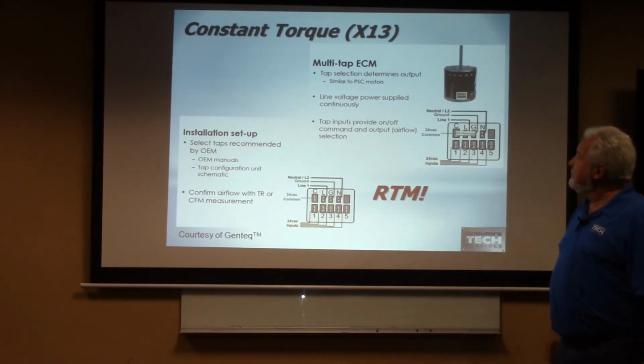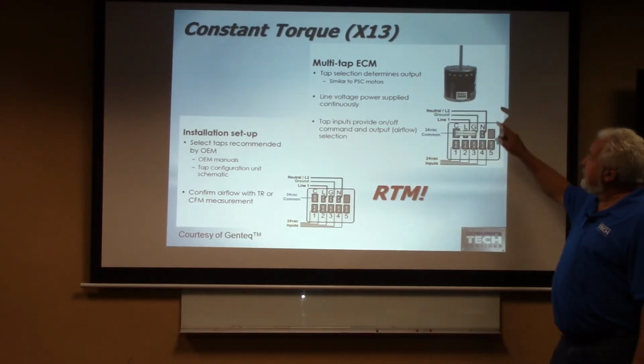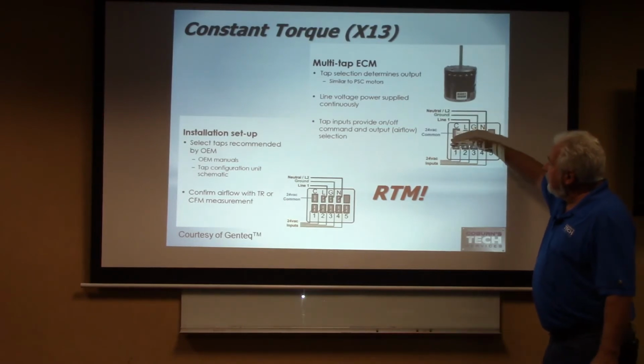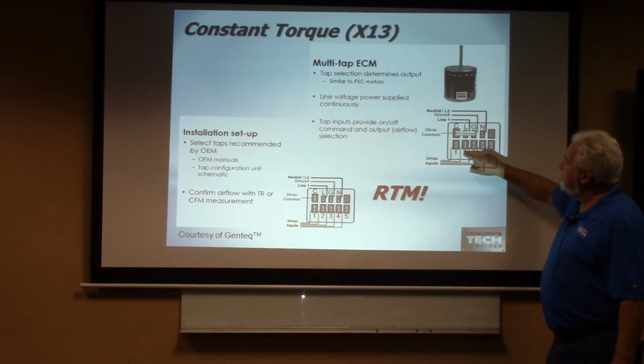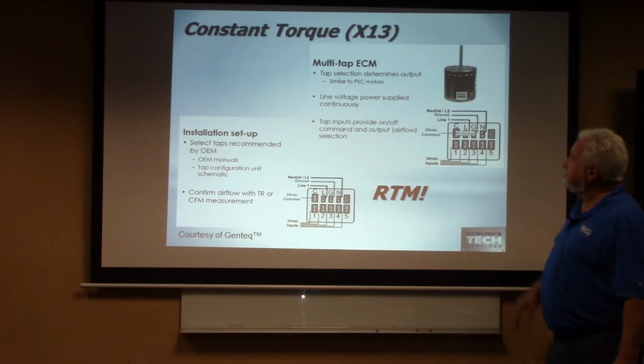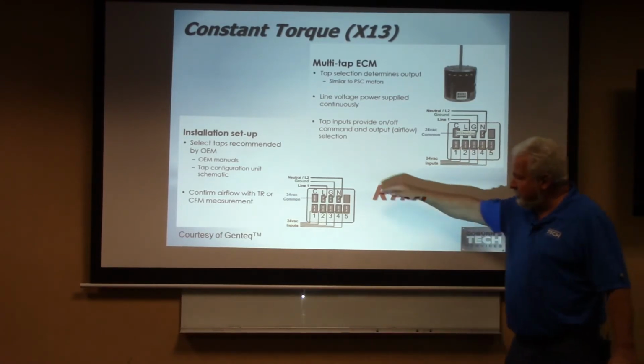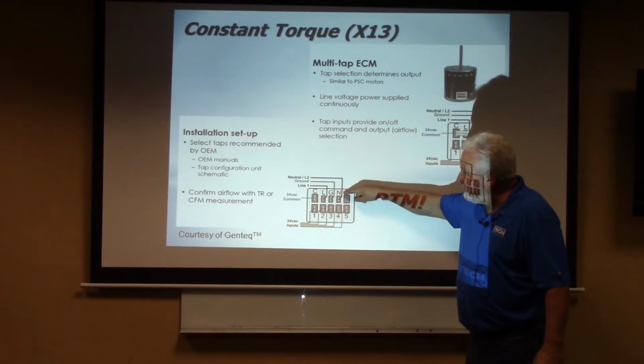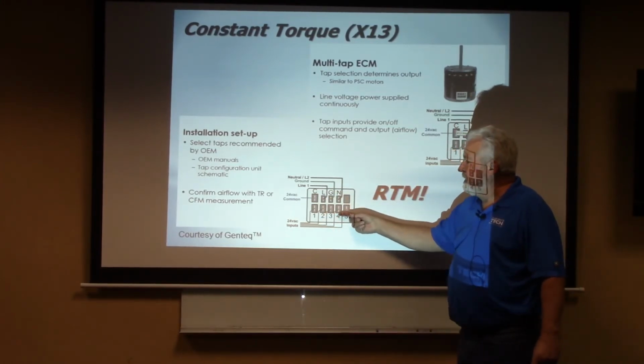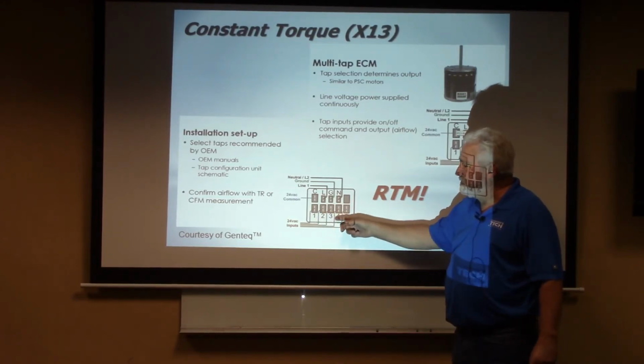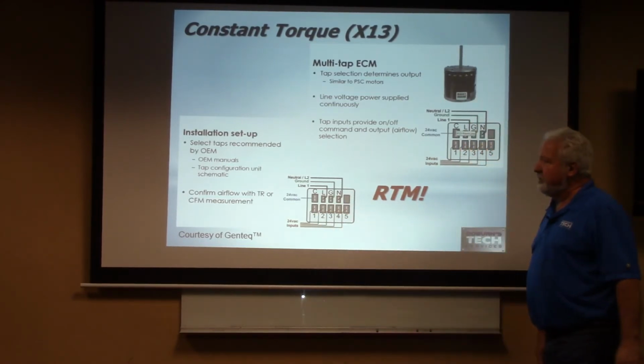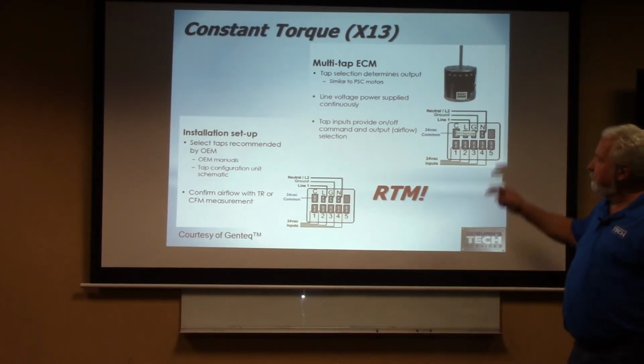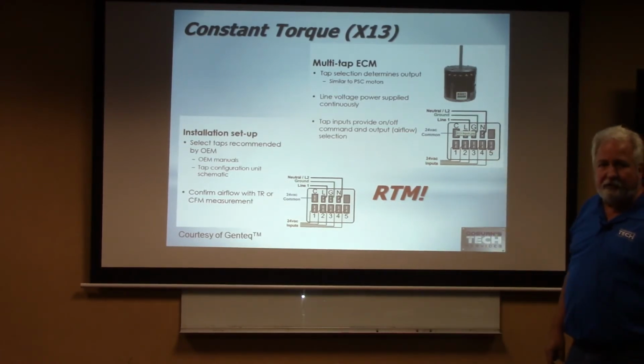So, constant torque. Again, we're going to have one set that's going to be our high voltage, and then the other one's going to be our 24-volt outputs on the bottom side. It's real easy. Here's my line voltage coming in, and then I got my 24-volt common, and then I have my inputs to that deal as well. So it's going to be 1 speed, 2 speeds, 3 speeds, 4 speeds. How many speeds it's going to be? You can always check first, do I have voltage applied? If you have voltage applied, then you start working backwards. Do I have the input voltages there?